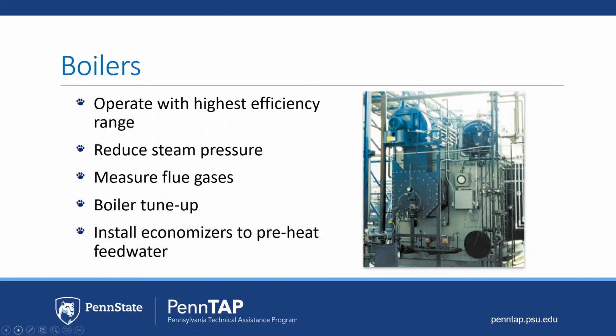Measure the flue gases to make sure that the ratio of air to fuel is correct. A boiler tune-up would correct this. Also, installing economizers to preheat the feed water. So this way the boiler is not doing all of the work to heat that water. It will save you money on your fuel bill.